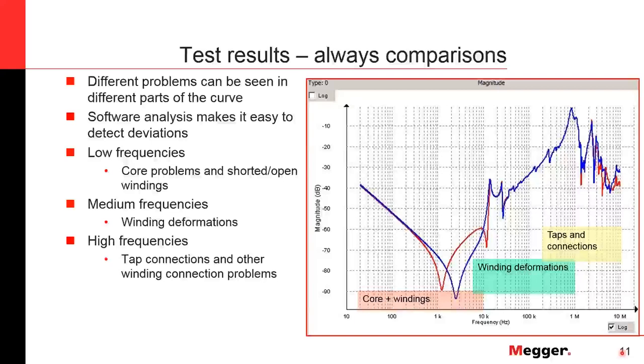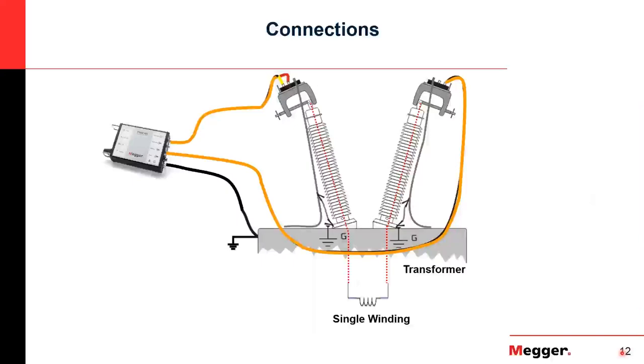In general, when looking at low frequencies, this is usually an indication of the core and how it's behaving, and a little bit of the windings as well. When we get into medium frequencies, you're really looking mainly at the windings. The first FRA devices were mainly used to look at windings, but by expanding to lower frequencies we found we can look at the core as well. And at very high frequencies, you're looking at taps, connections, and lead connections.